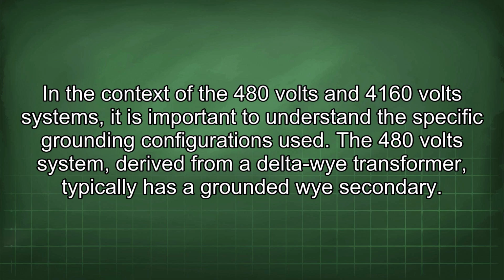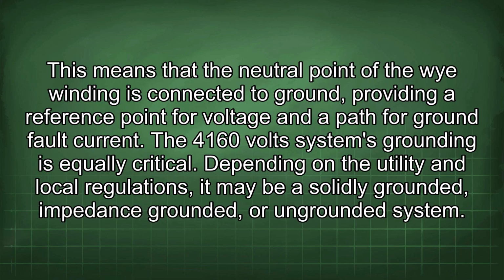In the context of the 480 volts and 4160 volts systems, it is important to understand the specific grounding configurations used. The 480 volt system, derived from a delta Y transformer, typically has a grounded Y secondary. This means that the neutral point of the Y winding is connected to ground, providing a reference point for voltage and a path for ground fault current. The 4160 volt system's grounding is equally critical. Depending on the utility and local regulations, it may be a solidly grounded, impedance grounded, or ungrounded system.